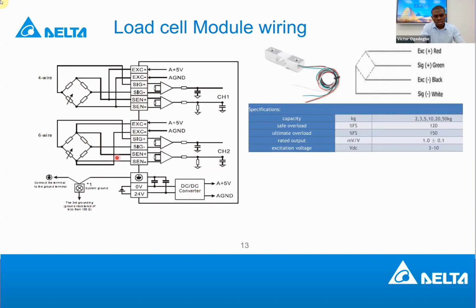And there's also a 6-cable configuration. There are some load cells or load sensors that have 6 wires. So this is how you also make the connection. It's basically like the 4-wire type. It's just that this has 6 wires, and the connection is more or less the same.